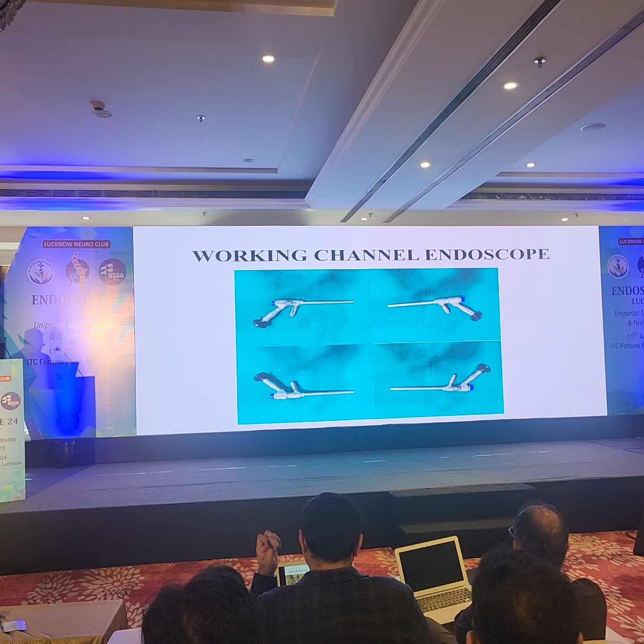I have this assembly. It is not 4K, it is just a full HD system. It is an all-in-one system. So the assembly is connected to the endoscope through a fiber optic cable. The blue color cable is the fiber optic cable. And then it is connected to a digital image processor. This digital image processor converts the signal received from the endoscope into a working image, which is projected onto the monitor.